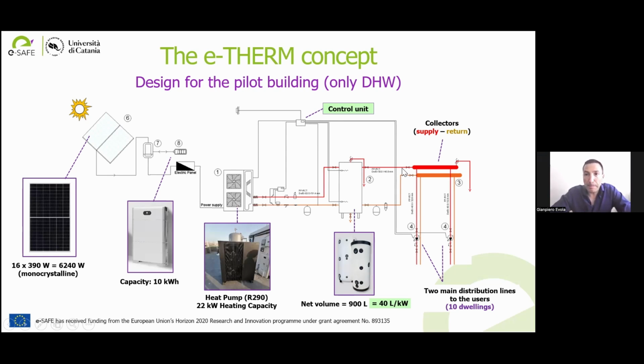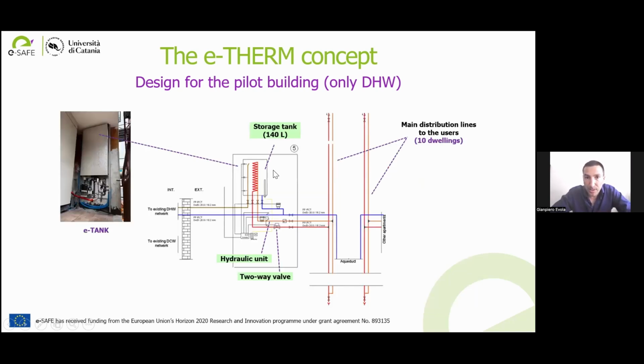The second difference is that while in centralized systems, water circulates in the pipes just when the users need water, in the e-THERM, water circulates more frequently because we have to thermally charge the e-tank, which means that the e-THERM system has more heat losses. So at the moment, according to the studies we have conducted so far, the two systems are more or less equivalent. e-THERM has higher heat losses, but can work with higher COPs. And in the end, the electric energy consumptions are quite similar. But these results can be improved because at the moment, we didn't optimize the sizing of the tanks and the control logics. So we have room for improvement.